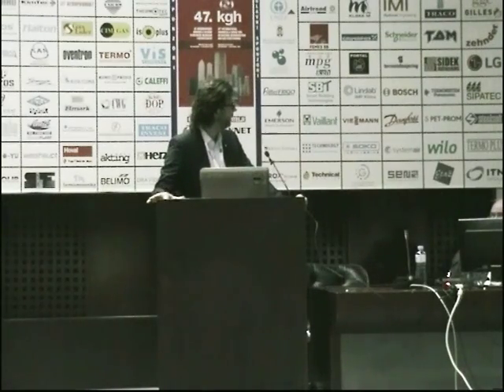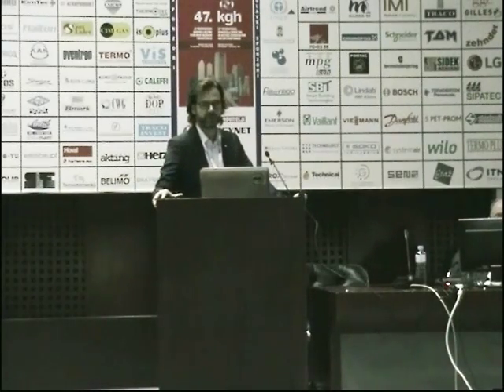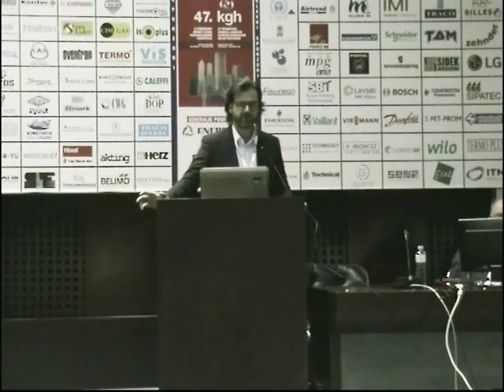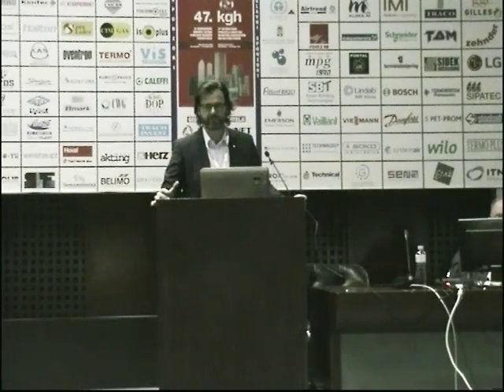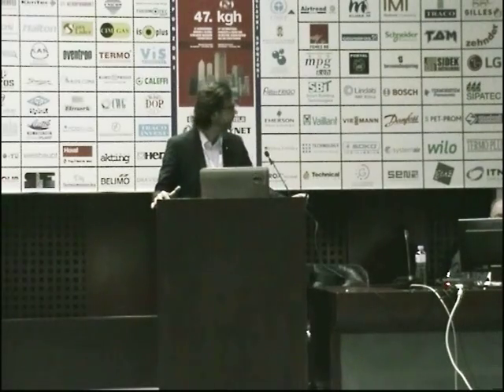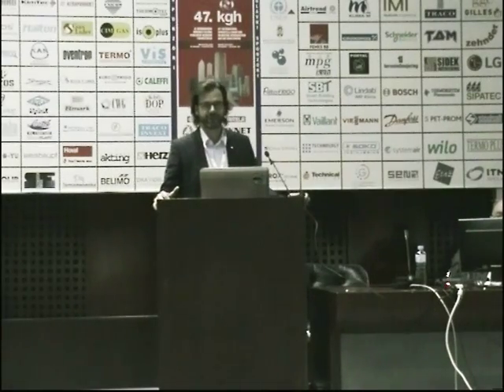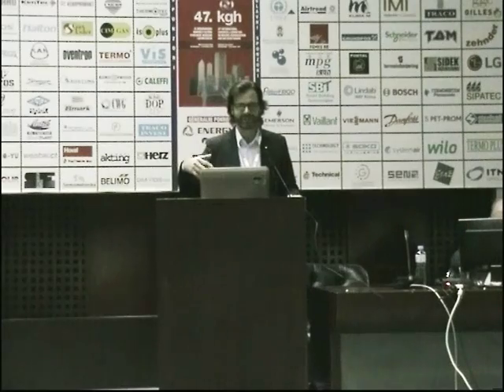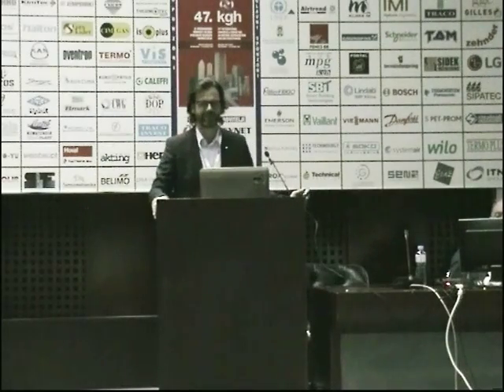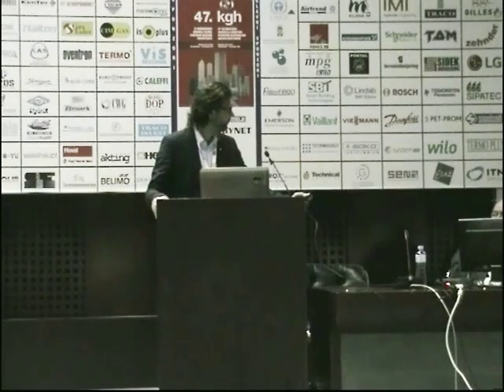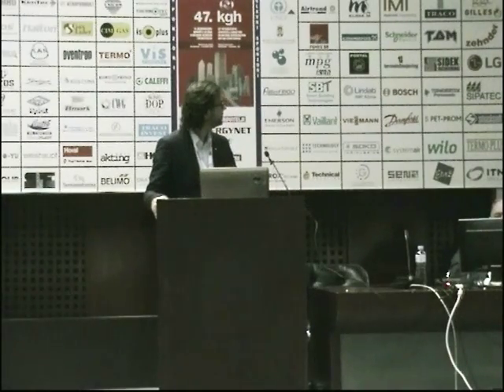And what we did in extra was calculating the secondary loop system: dimensioning, vacuum, deaeration, pumps. In South Africa they already had a secondary system, but with a lot of corrosion in it, which really did not work. So we did the calculations with the manufacturers. We worked till Friday, and on Saturday we sat and did dimensioning and calculation in the offices. So we calculated the pipework and the valve stations with them, and some thoughts on efficiency came out of it.